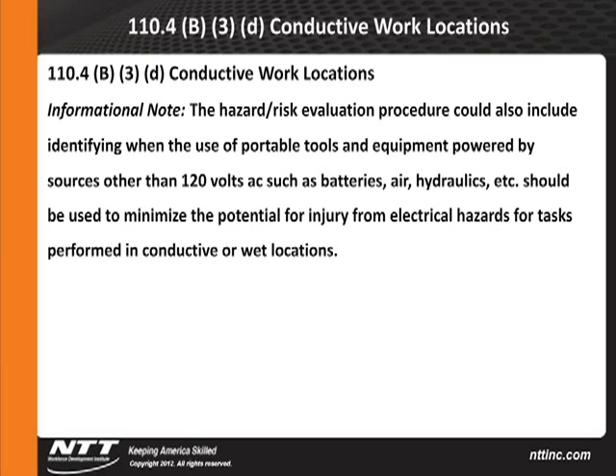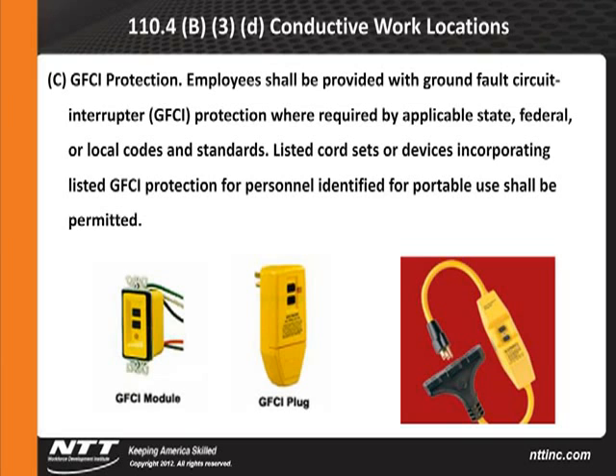So how do we protect people out there then? This is a part that's been added into the standard, GFCIs. Employees shall be provided with a ground fault circuit interrupter, a GFCI, where required by applicable state, federal, or local codes and standards. Listed cord sets or devices incorporating listed GFCI protection for personnel identified for portable use shall be permitted. So again, are we using them? Basically what we're talking about is that GFCI needs to be on the plug-ins, the receptacle I'm plugging my tool or my extension cord into, to protect both the cord, the tool, and the individual using it.